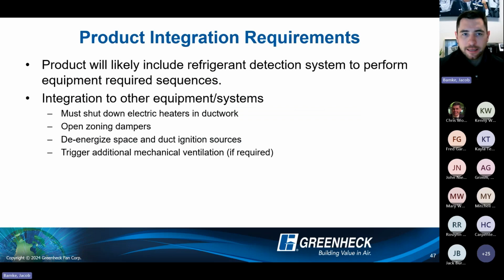All right, so how do we integrate these products, specifically outdoor air type equipment? The product itself likely will have a refrigerant detection system to perform whatever required sequences we have to, to make sure we are meeting the safety standard, UL 60335. However, there are things downstream that we have to integrate to and make sure that everything downstream is handled effectively with leaking refrigerant as well.